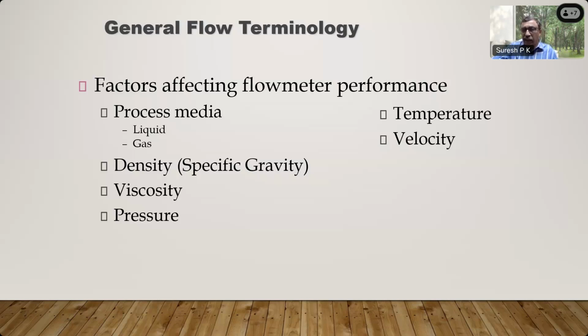The cost is one thing. You have to consider whether it works properly and reliably for a long duration of time under the conditions of operation. This is also important, because suppose you have specified a temperature of 50 degrees centigrade or 60 degrees centigrade. Unfortunately, the process temperature goes up to 80 degrees centigrade, and suddenly the flow meter goes out of order. That kind of reliability. We need a little more reliability, a little more safety factor for the flow meter selection.